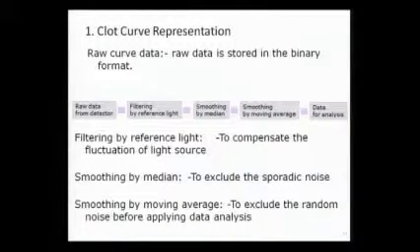So the important thing is, whenever you have a coagulometer which has a screen and you are able to see the clot curve, it's a nice habit to look at the clot curve, because it's probably a requirement for the validation process to see whether the APTT and the PT, when the clot is produced, produce a very neat curve, and there is no background noise. If the background noise is there, probably you can have an indirect check on the optics of the whole system.